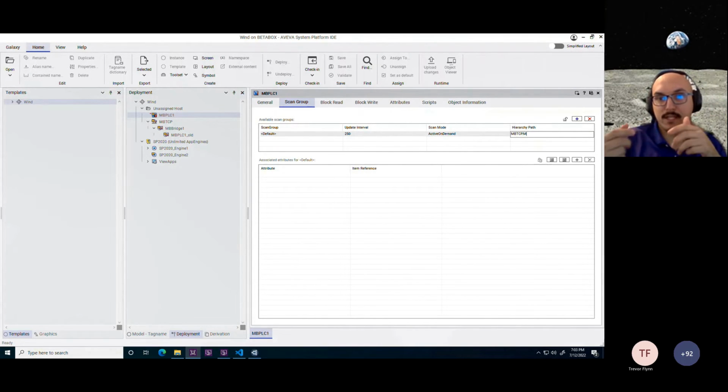In this case, you'll see the bridge or the driver, and then the bridge syntax, as well as the rest, inputted there. Now it's telling that OPC client to use the previous existing configuration, where the attributes of System Platform were acquiring their data from that Modbus OI server. So being able to move away from those objects into something that's newer and supported going forward.